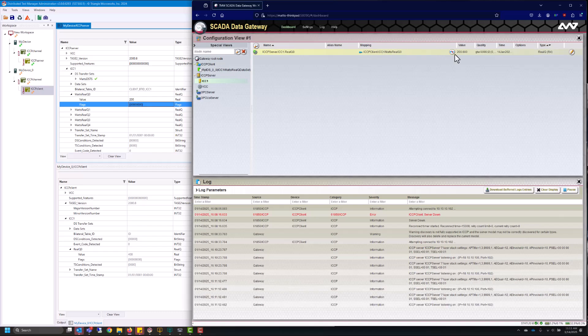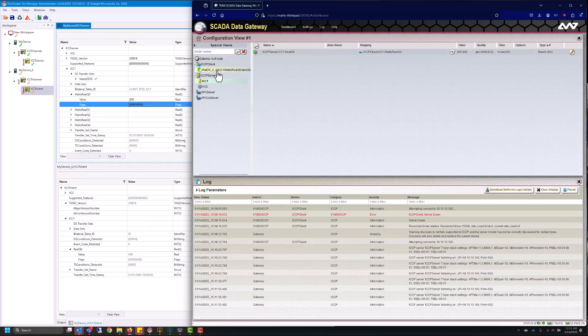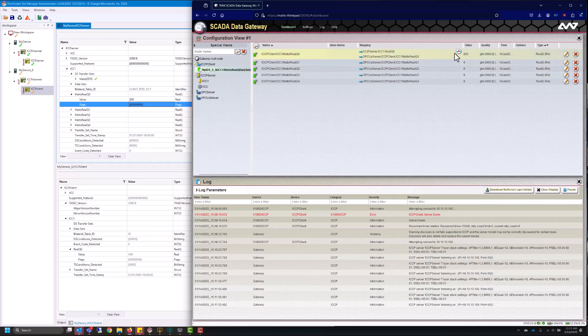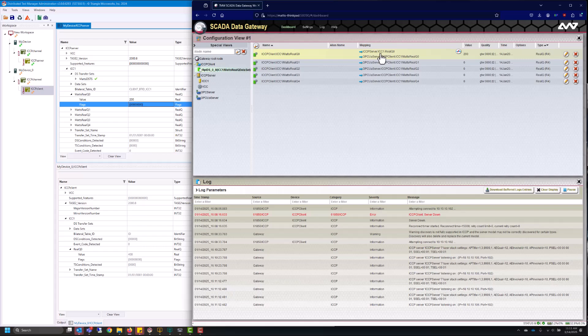You can clear this mapping in two ways you can click the delete mapping button right here in the ICCP server or you can go to the source which is the ICCP client and you'll also see a delete mapping button. The arrow indicates which way the mapping is going so this RealQ is being mapped to ICCP server ICC1 RealQ0.